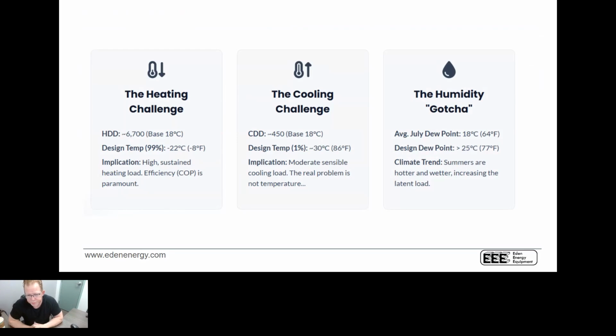So the cooling challenge that we have is typically cooling degree days. It's about 450 cooling degree days. The worst case we'd see is somewhere around 30 degrees C, 86 degrees Fahrenheit, although I'm pretty sure this past summer we saw some very, very hot temperatures. It's a pretty moderate, sensible cooling load. And the real challenge with cooling with an air to water system is not really the temperature, it's the temperature and the humidity. The summers are getting hotter, but they're also getting wetter, and we're seeing increased latent loads.